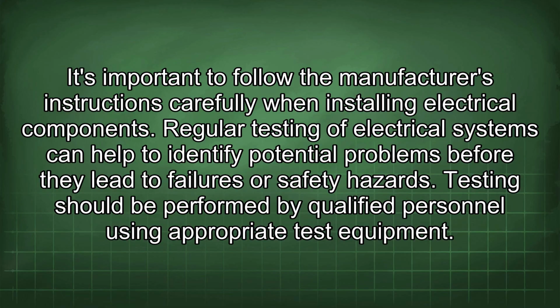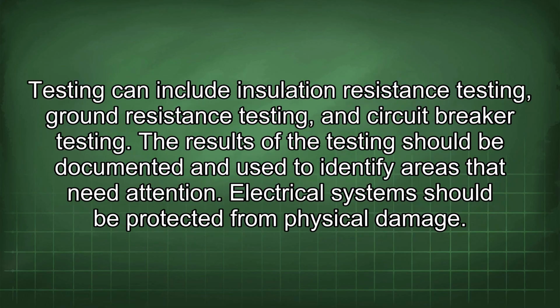Regular testing of electrical systems can help to identify potential problems before they lead to failures or safety hazards. Testing should be performed by qualified personnel using appropriate test equipment. Testing can include insulation resistance testing, ground resistance testing, and circuit breaker testing. The results of the testing should be documented and used to identify areas that need attention.